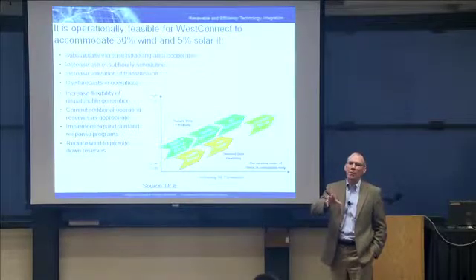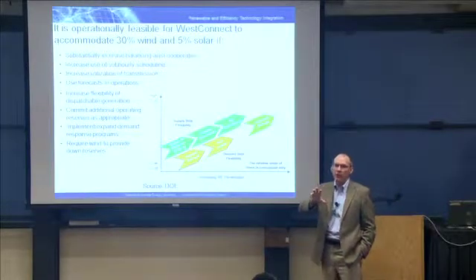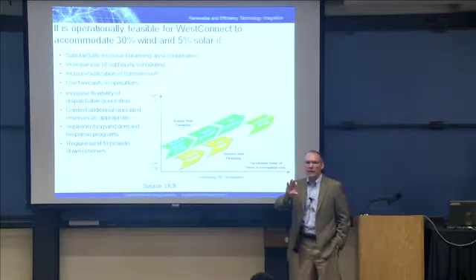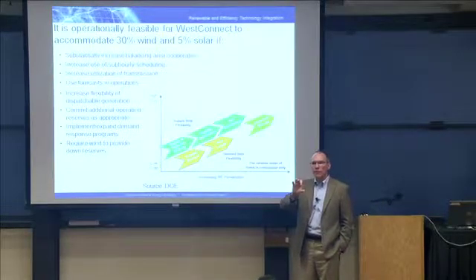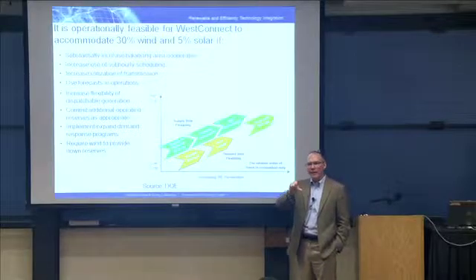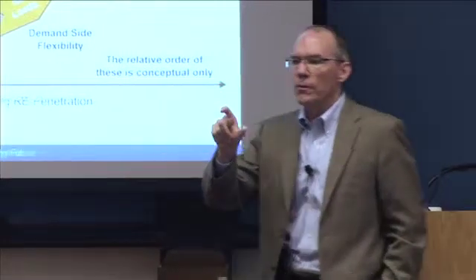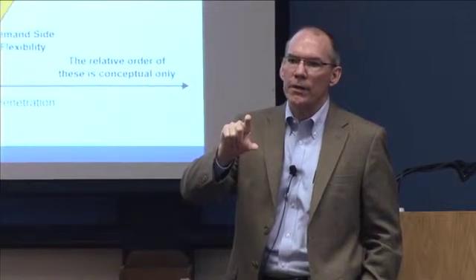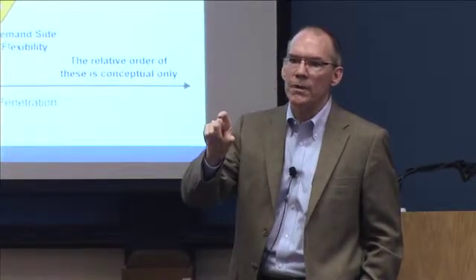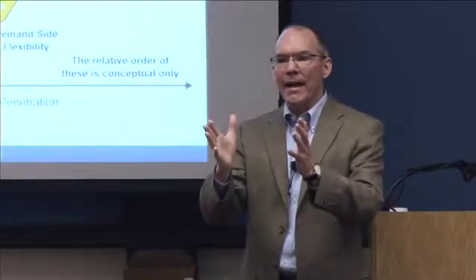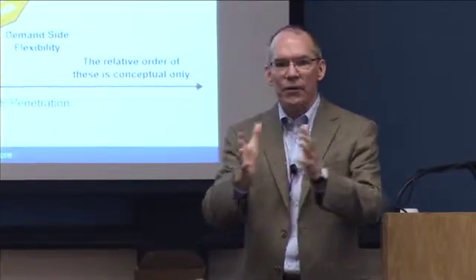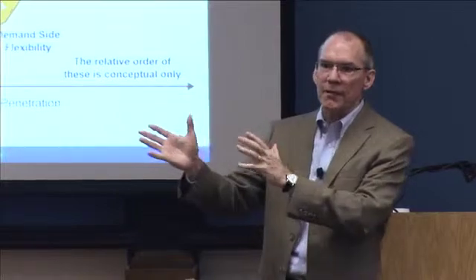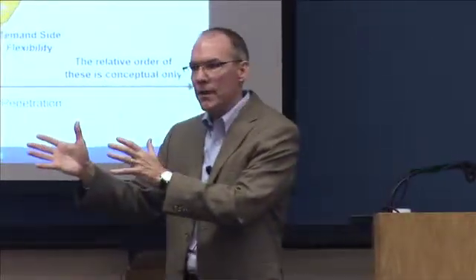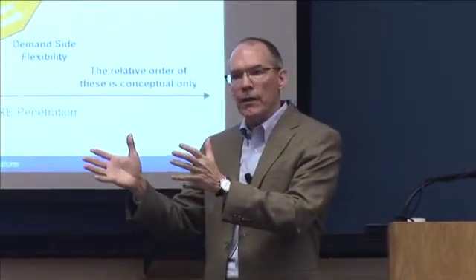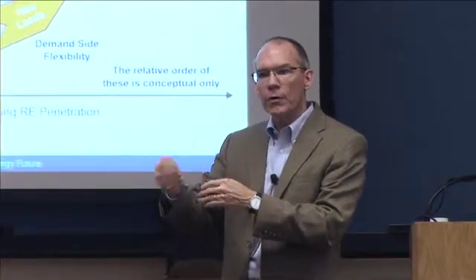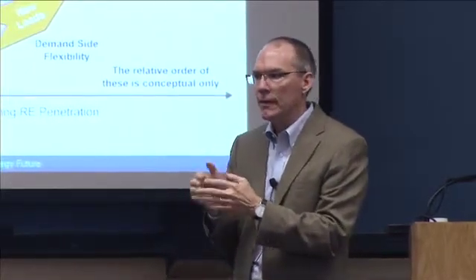Right, it would get worse with higher penetrations. The requirement right now is that you have to have 6% of your demand available at any point in contingency reserves - 3% spinning and 3% non-spinning. So to meet those reserves you have to add additional spinning reserves. You don't know when those 89 hours are going to occur, which is one of the challenges, so you have to keep them on 24/7, 8,760 hours a year, which is very expensive. So in the next phase of the study, we're looking specifically at that.